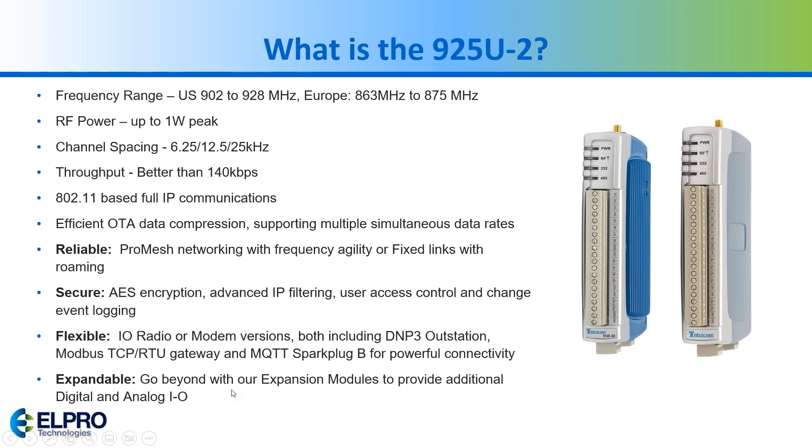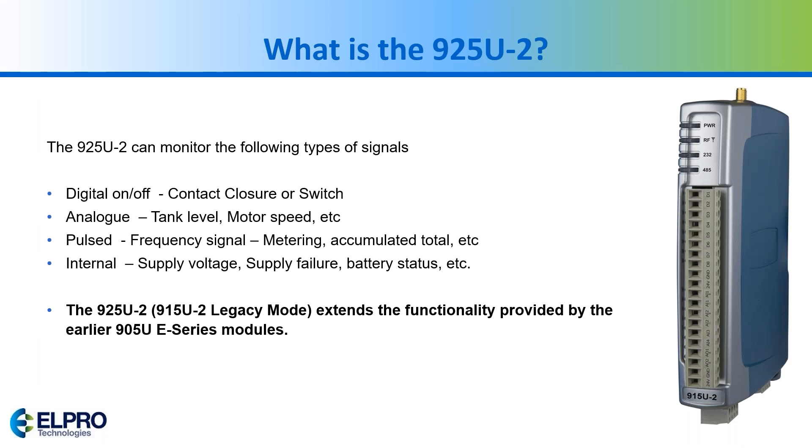It communicates over Modbus RTU and Ethernet — I'm going to show an example with Modbus RTU. It also has eight digital I/Os, four analog inputs, two analog outputs, and pulse inputs and outputs. You can access internal registers to look at voltage levels and signaling failures. It can be put into legacy mode to replace the 915U-2, and it can also replace the 905 units.